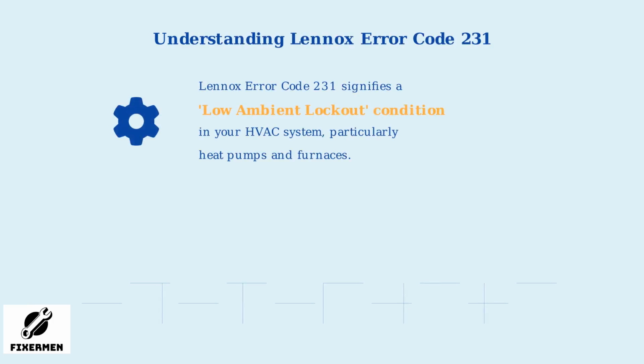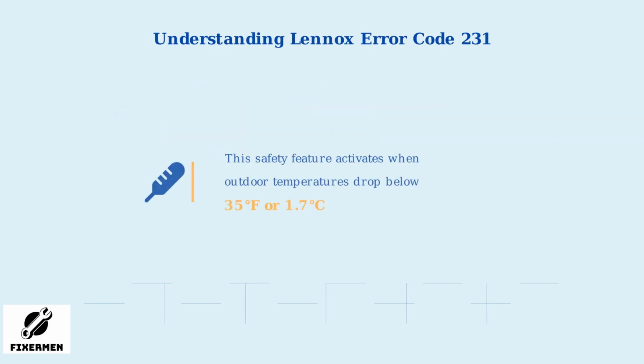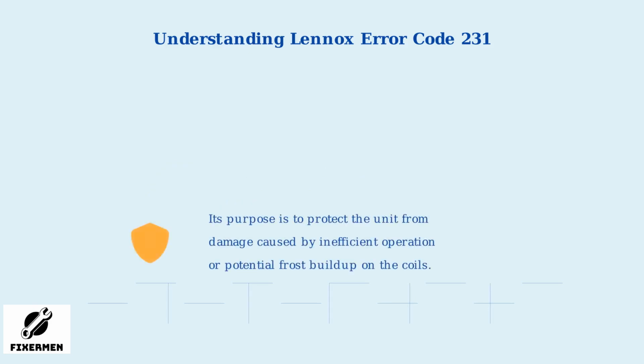Lennox Error Code 231 signifies a low ambient lockout condition in your HVAC system, particularly heat pumps and furnaces. This safety feature activates when outdoor temperatures drop below a set threshold, typically around 35 degrees Fahrenheit or 1.7 degrees Celsius. Its purpose is to protect the unit from damage caused by inefficient operation or potential frost buildup on the coils. In essence, it's a protective measure, not necessarily a malfunction.